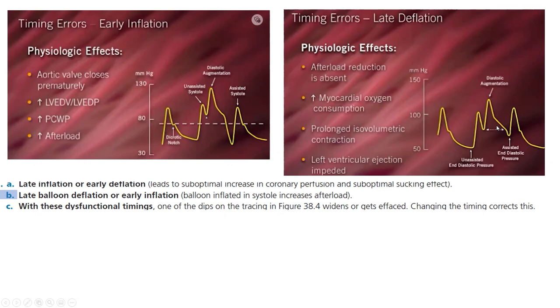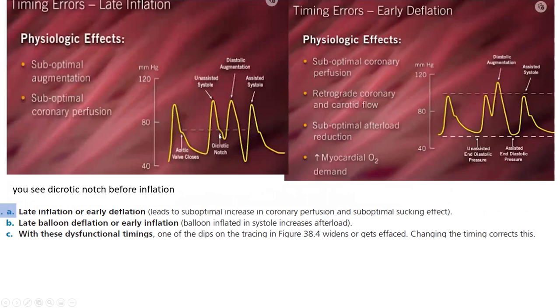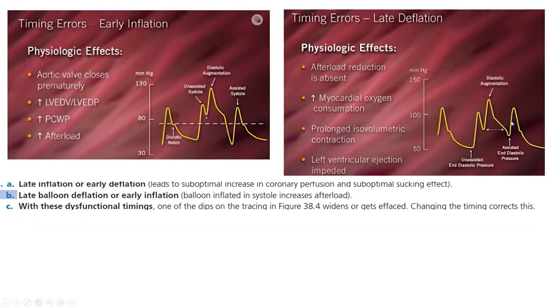And here you're deflating very late. So when you deflate very late, your assisted diastolic pressure and end-diastolic pressure are not going to be lower than the unassisted one. So always go back to that basic concept. You should not see the dicrotic notch. You should not see the dicrotic notch. And your assisted systolic and diastolic should be lower than the unassisted. Okay.